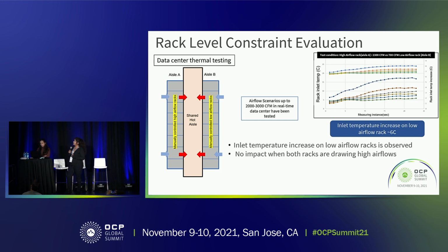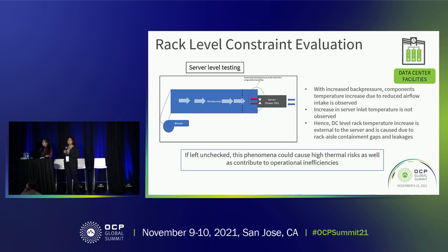What we have also seen in this test is that when both the racks are in high airflow condition, like 2,300, for instance, we wouldn't see any increase in inlet temperature. So we wanted to understand what could be the main reason for this. Is this contributed due to any internal recirculation that happened within the server because of the back pressure and the low pressure regions within the server, or is this external to the system?